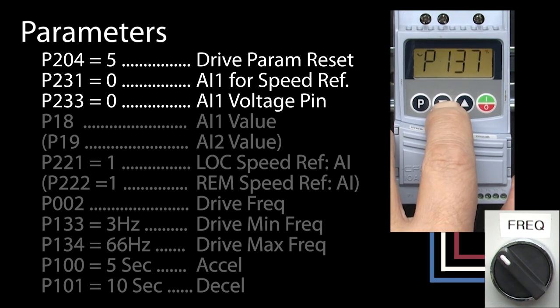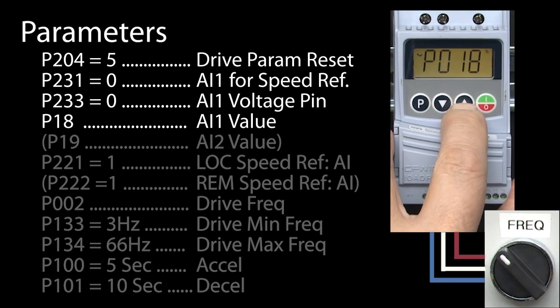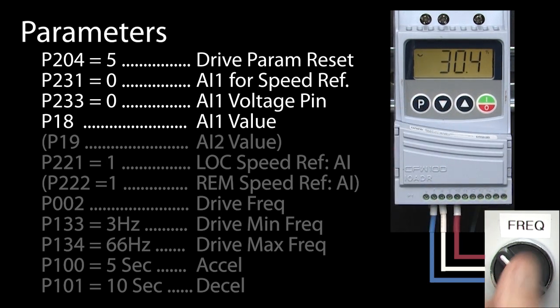To verify we did all of that correctly, we can go to parameter 18, which shows us the value the drive sees on analog input 1. Rotate the potentiometer, and sure enough, full counterclockwise gives me a zero reading and full clockwise gives me 100%. Perfect. I'm going to put that back at zero so we don't get any surprises when we connect that to the motor.